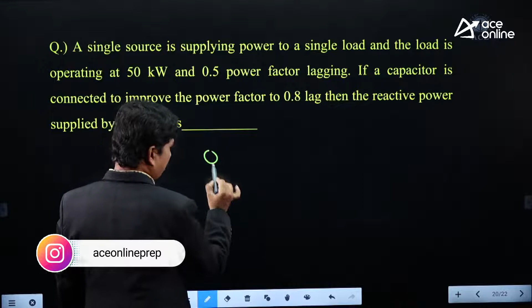Very simple. We can directly write the formula here. The reactive power supplied by the capacitor, QCSH, is equivalent to P into (tan phi 1 minus tan phi 2), if you remember the formula, where P is 50 kilowatt. Cos phi 1 is given as 0.5, so tan of cos inverse of 0.5 minus tan of cos inverse of 0.8, which is the second power factor. If you calculate that, that will be the resultant reactive power.